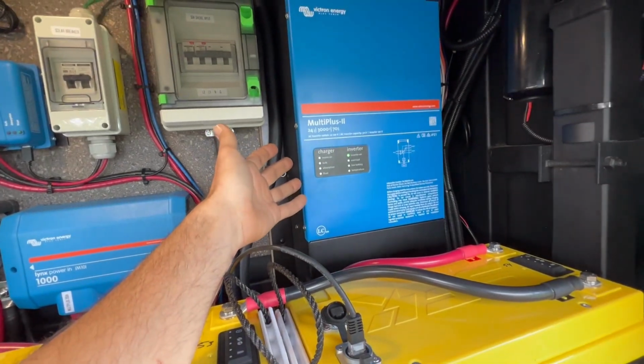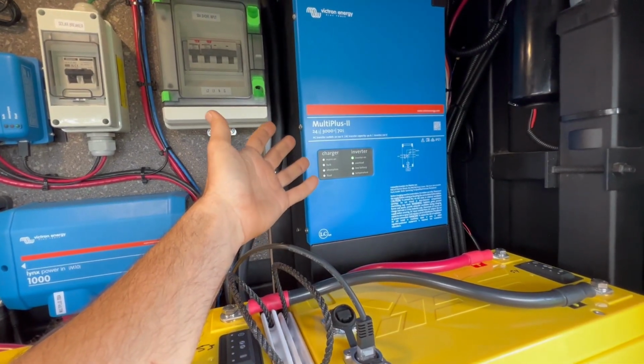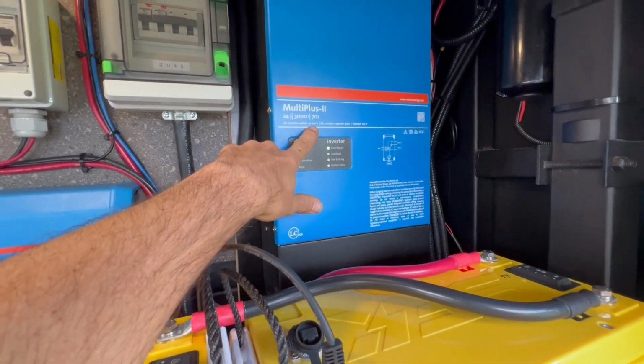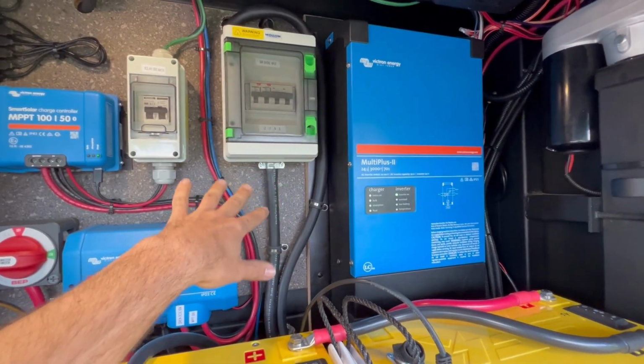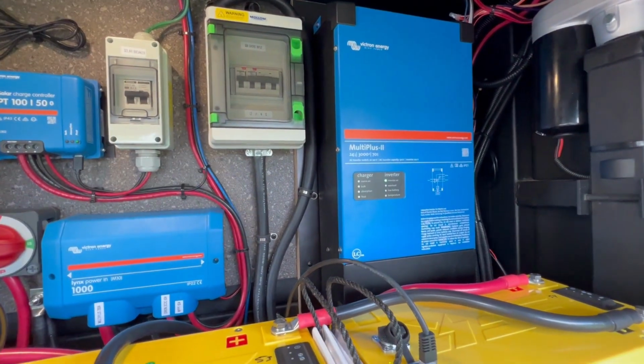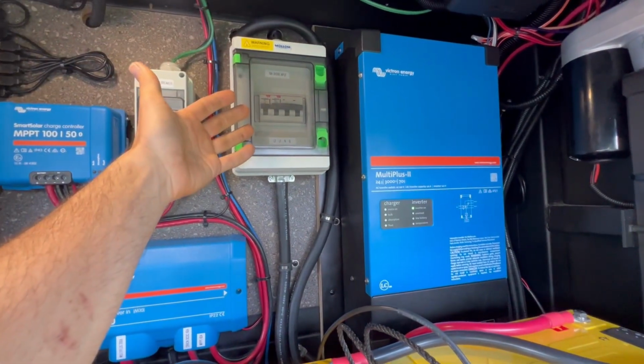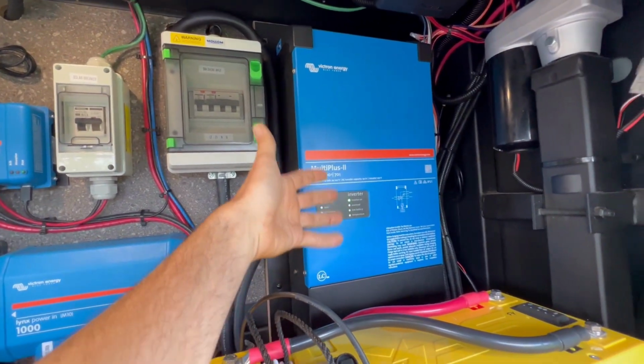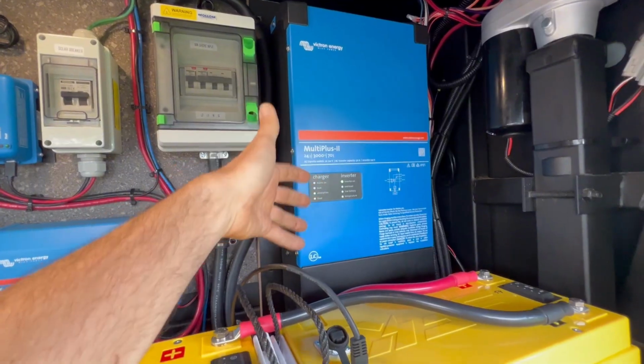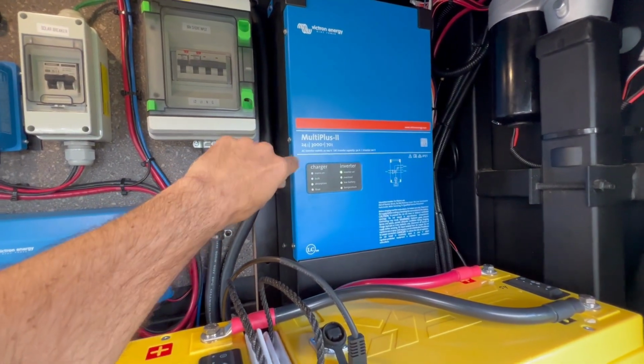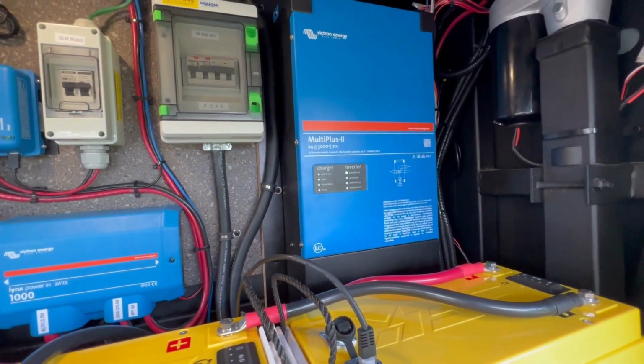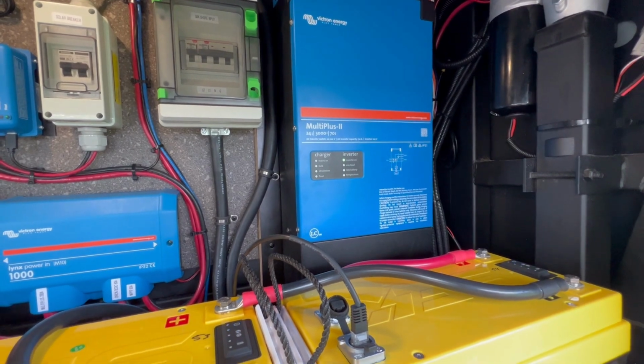We're using a 24-volt 3000 VA Multiplus 2. This is a 2x120, meaning that the 50 amp shore connection that powers this rig comes in through our breakers and comes into our Multiplus. So this can pass through the 50 amps, but on battery power only, it's able to put out the 3000 VA.